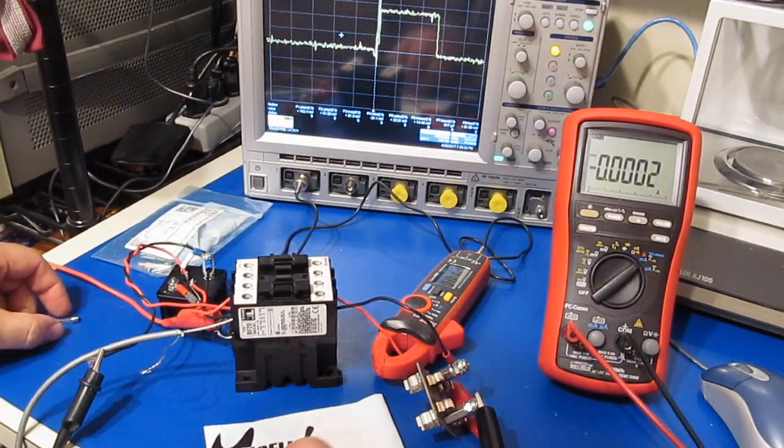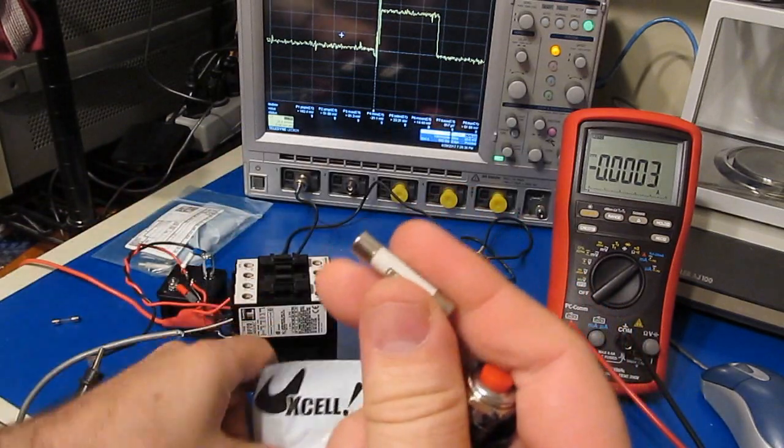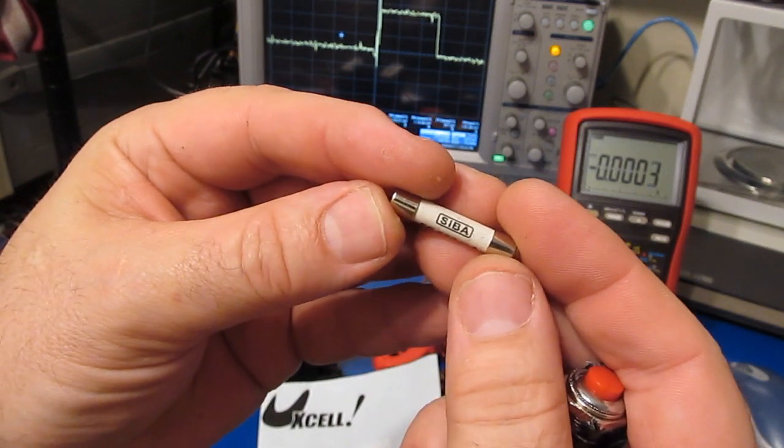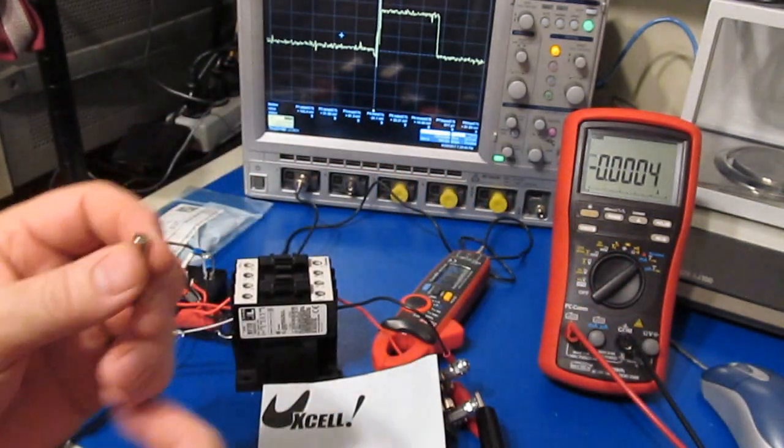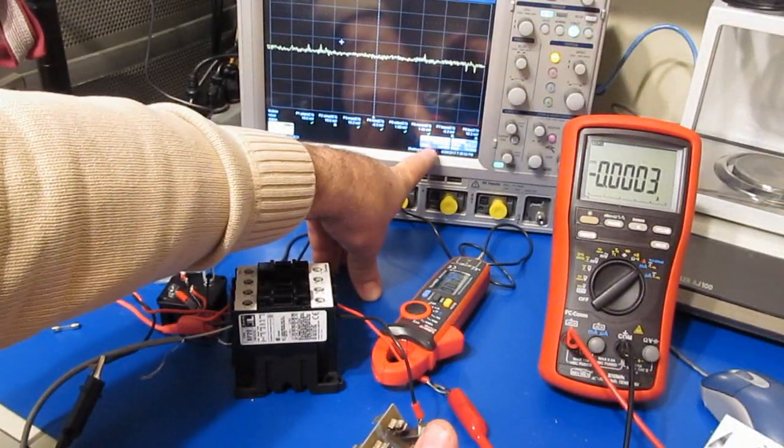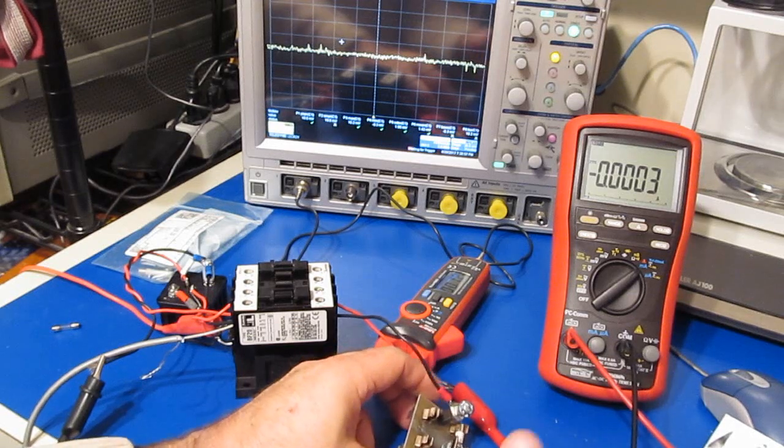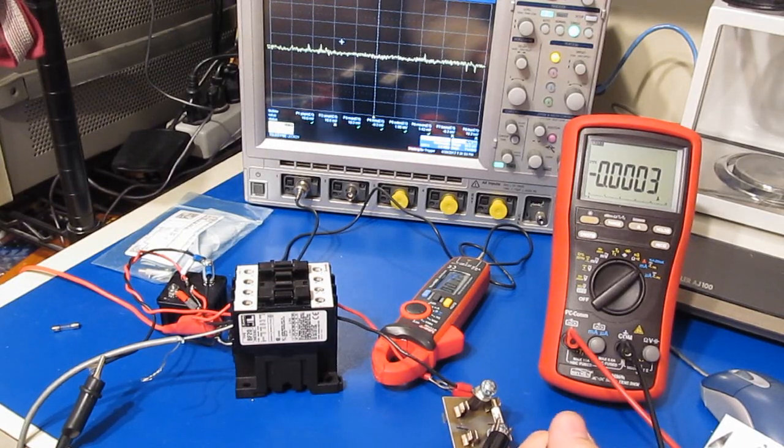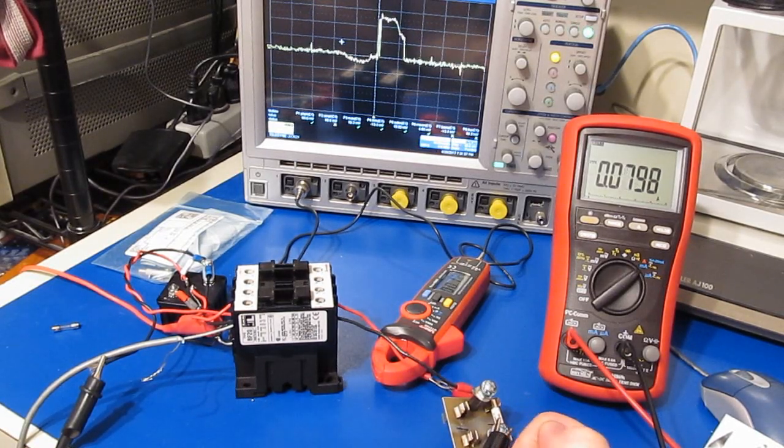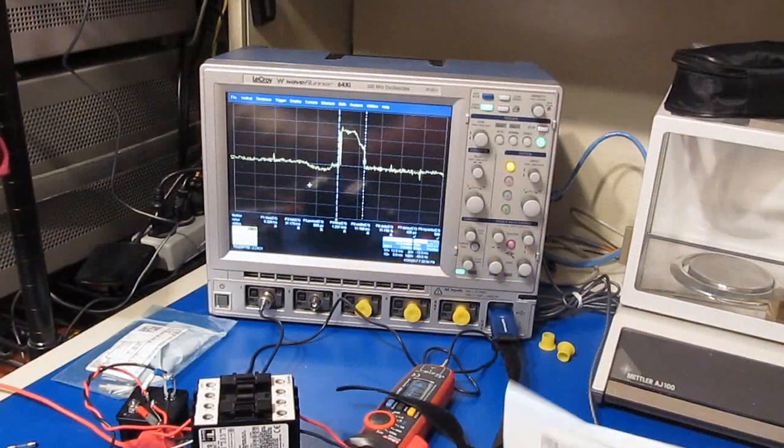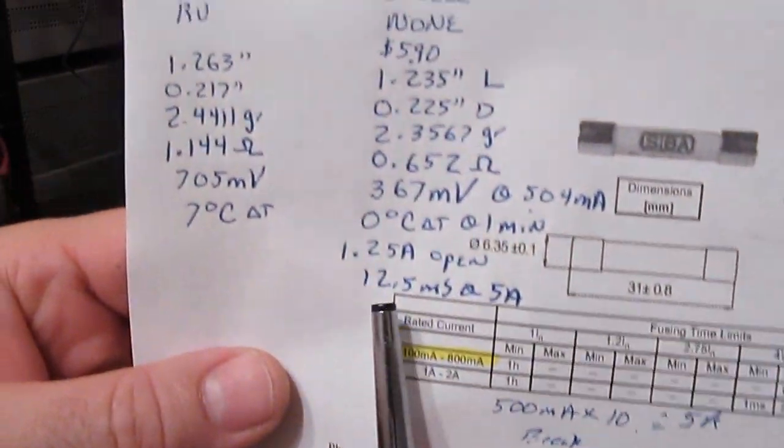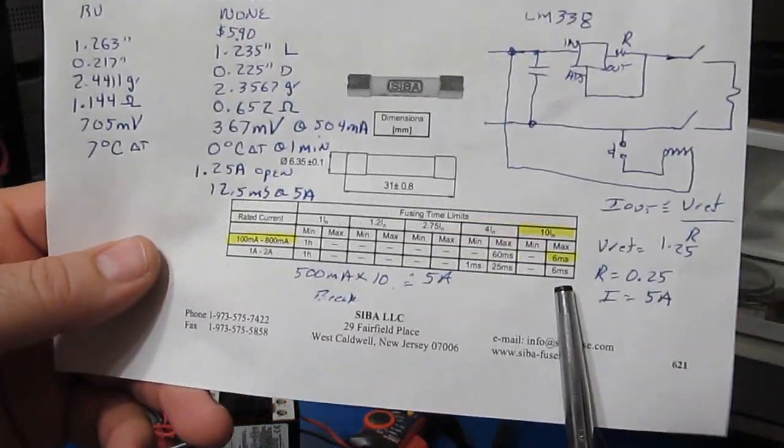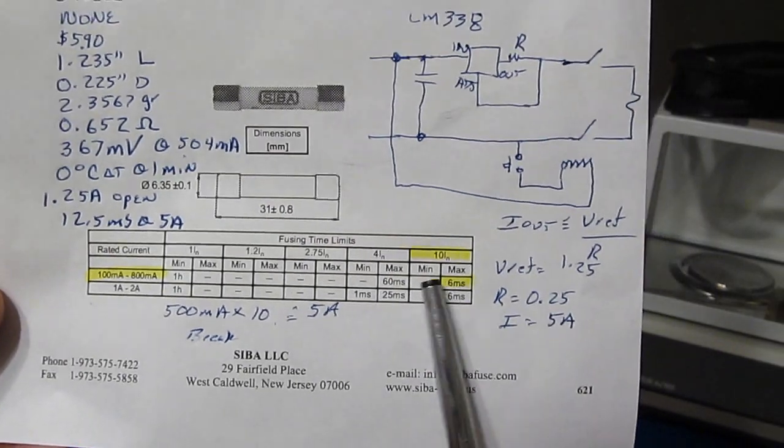What we'll do next is install this last fuse here and let's just see what happens. Again, this fuse should open up in under 6 milliseconds. And just for a reference, it looks identical to the first fuse that we looked at. What I've done is I've changed our scope to 10 milliseconds per division. Hopefully we'll be able to actually catch it with it set to single shot. And here you go, three, two, one. Wow, look at this. So our break time is roughly 12 and a half milliseconds at 5 amps. And this is about double what the Siba manufacturer calls for.